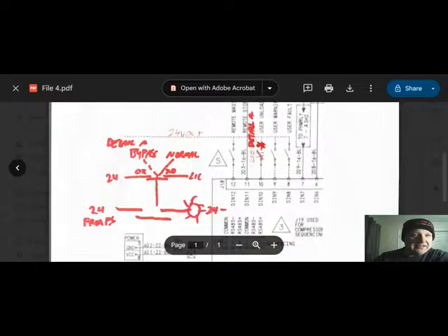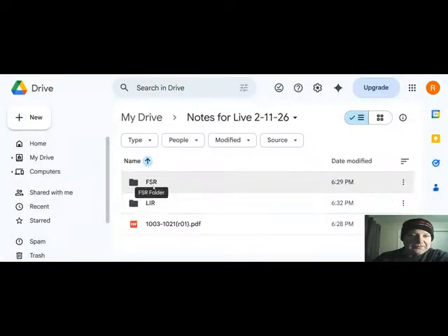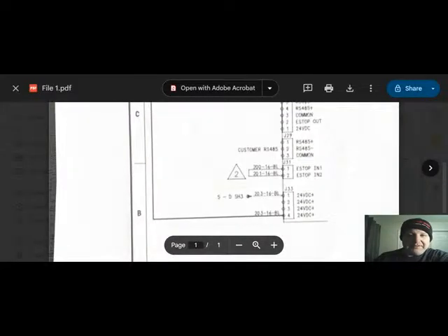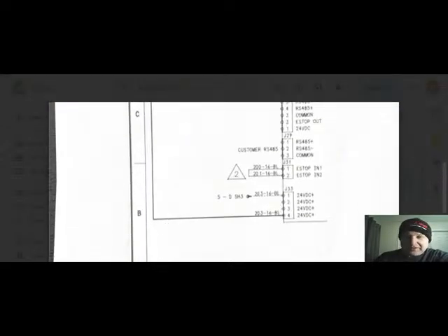The other example I shared in the original post was if you are going to tie an emergency stop circuit in the fire suppression relay. Not all compressors have this, but on the Solar, if we are lucky enough, we have a secondary e-stop input. You could do this just as easily, interrupting your regular e-stop circuit as well. You just have to know if that e-stop faults on an open or a close, and you can set your wiring up accordingly. But we have a secondary e-stop input here, so that's what we are going to use.